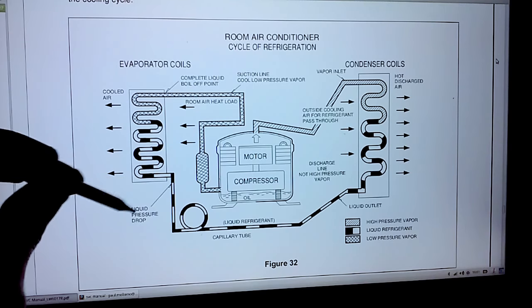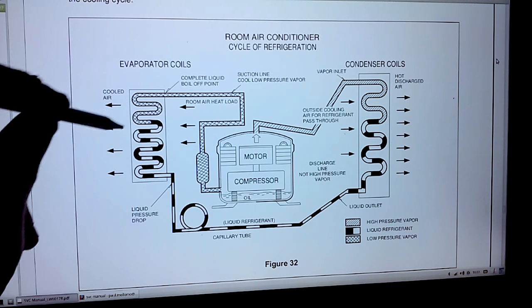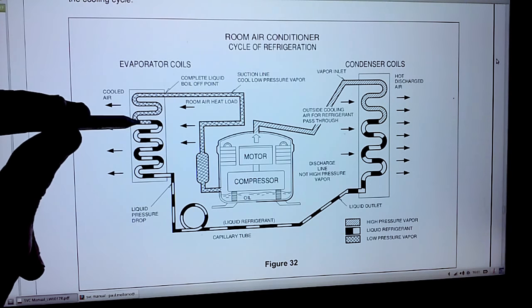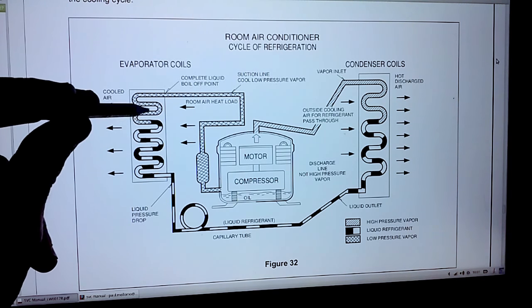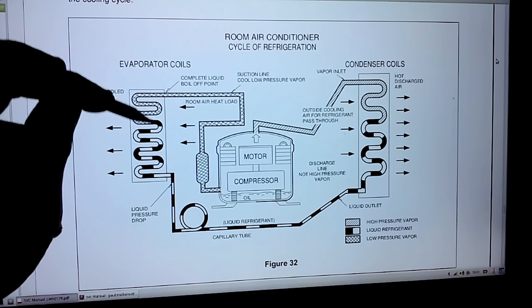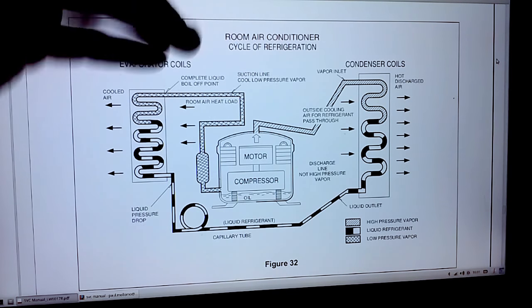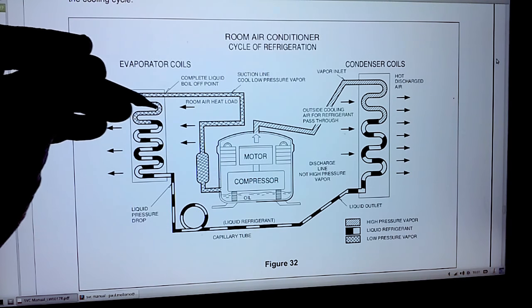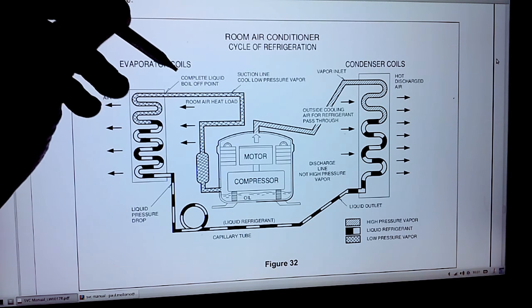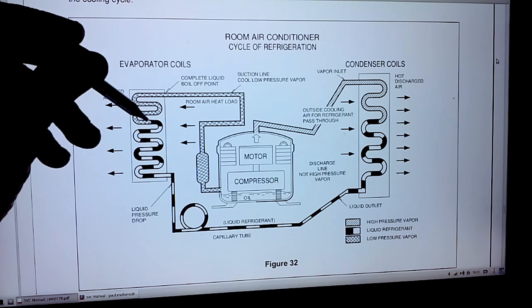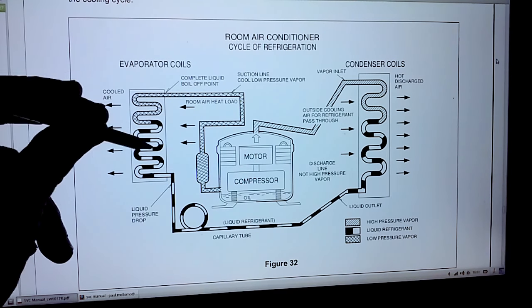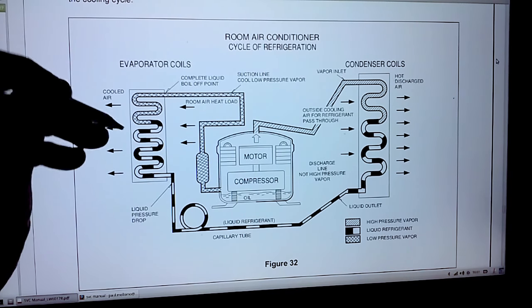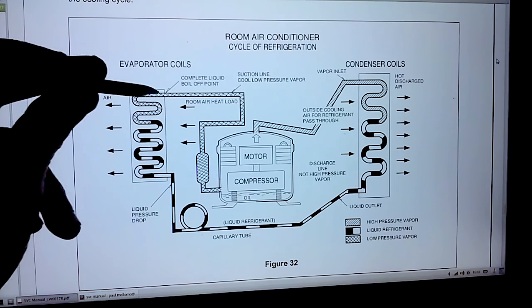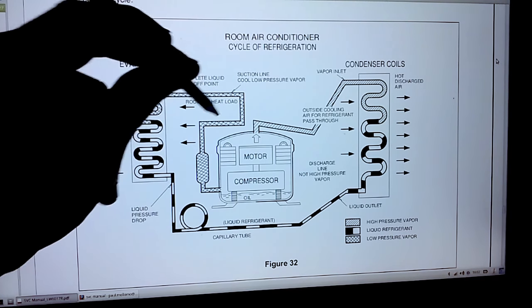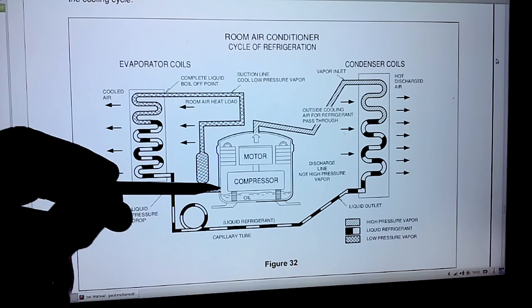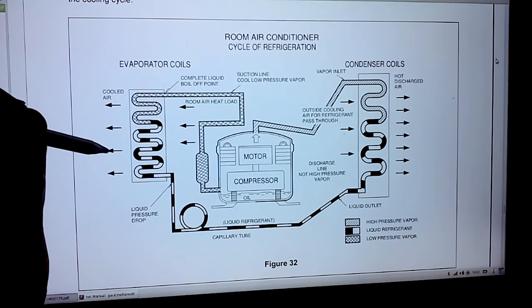And as this liquid pressure drops, as it reaches the front of the unit, as it were, you can see we're reaching the crosshatch area where the balance between the liquid refrigerant and the vapor is met right there, at which point this is low pressure vapor. And here we have the complete liquid boil off point. So the liquid refrigerant is no longer in a boiled state after its cool air is ejected out the front of the unit. Now we have low pressure vapor, which is fed back into the compressor, and the cycle repeats.